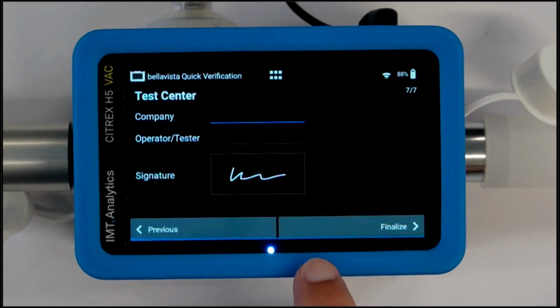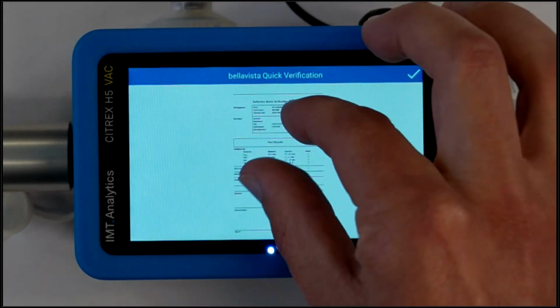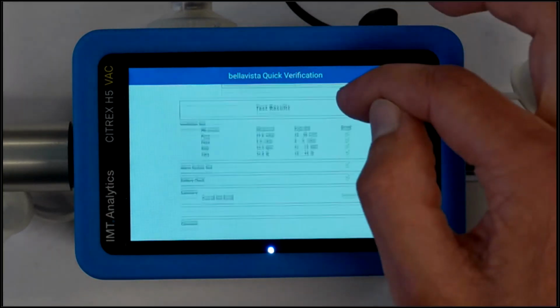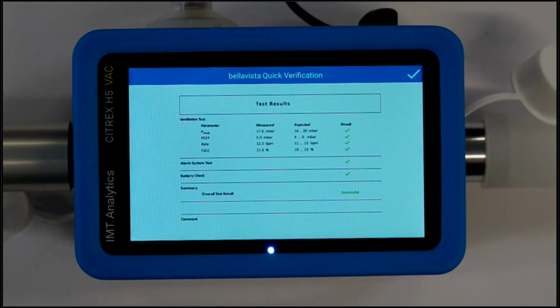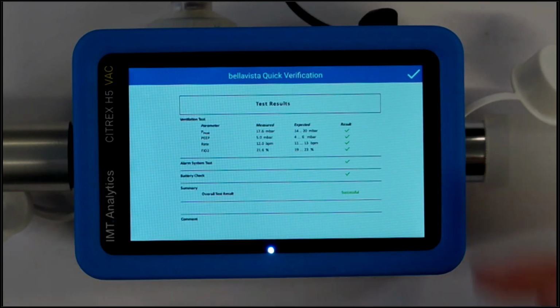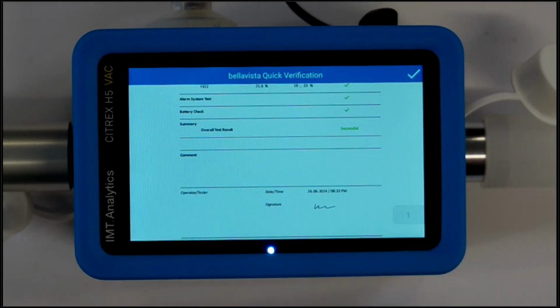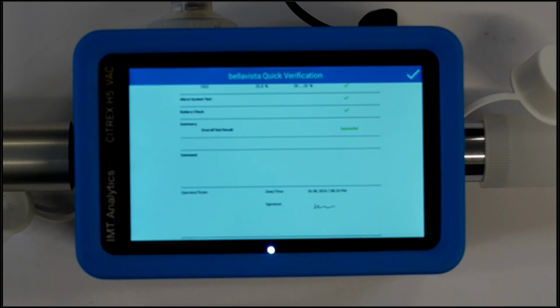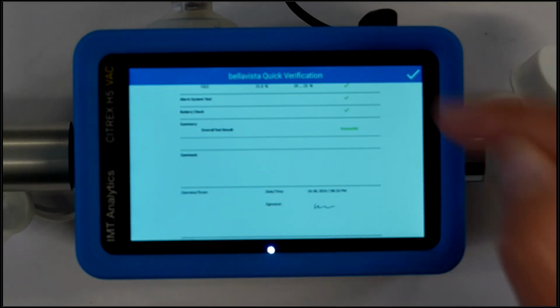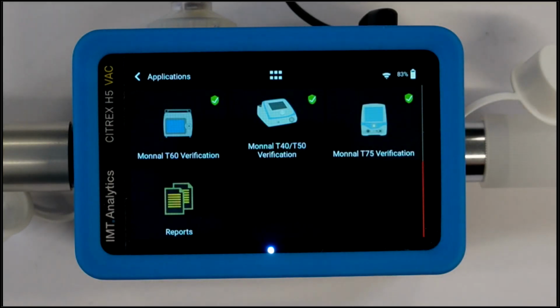Once I'm done with that, I can finalize the report. And as you can see, this is the report. I can view it on the screen. I can zoom in, zoom out, and you will see that it contains all the measurement results, all the actual measured values, and additional documentation we did. So you have objective proof that you have tested the ventilator against the manufacturer's specifications. Once I close this, the report is being stored in the internal memory of the device.